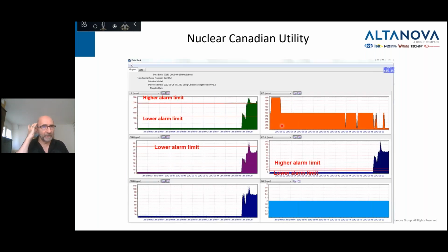Here's another example where the response time and the accuracy are absolutely critical. It happened a couple of years ago in a Canadian nuclear plant after a maintenance, where after the startup, something broke down in their transformer, and you can see in a matter of less than 24 hours, a major catastrophic increase of all the gases, especially the hydrogen, the methane, the ethylene, and the most critical of all, the acetylene, which went up as high as 110 ppm. So again, especially if you have a critical transformer, like in a nuclear plant, the accuracy and the response time of any kind of system you put on those transformers is absolutely important, to be able to make the right decision in a timely manner.